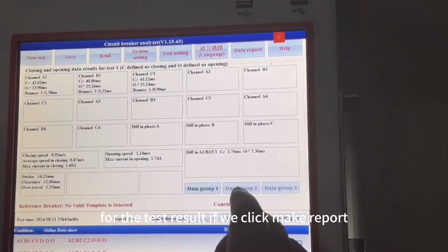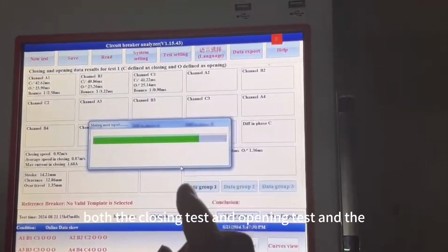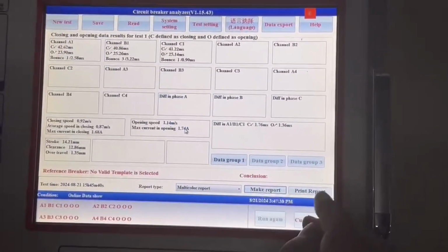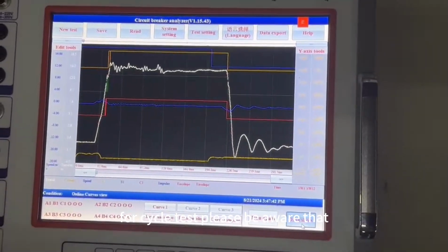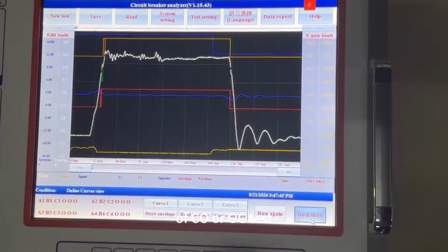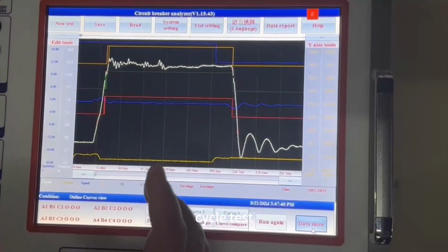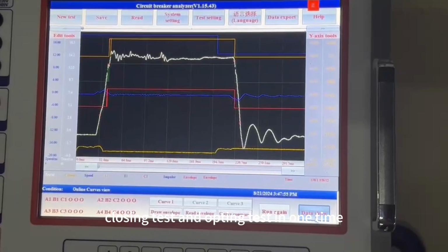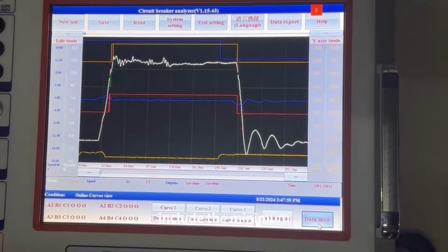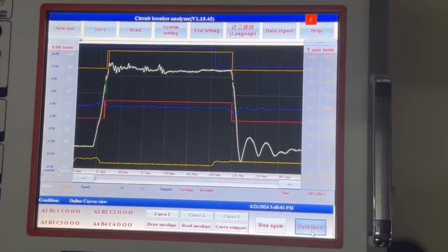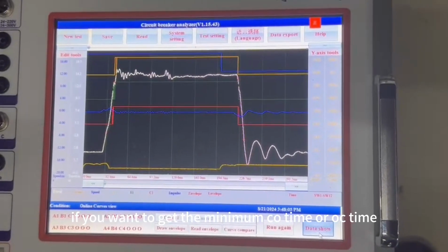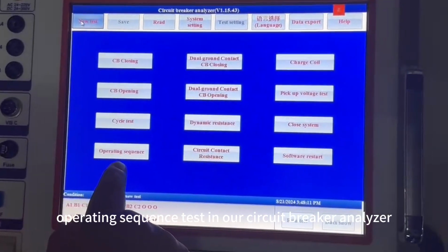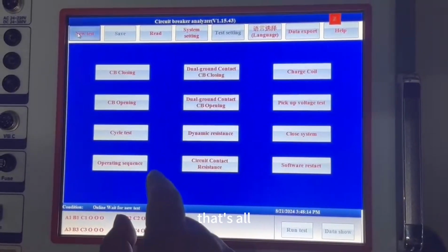For the test result, if we click make report, both the closing test, the opening test and the CO test curves will be saved in one report. For circuit tester, please be aware that it is different from CO tester or OC tester. Circuit tester in our circuit breaker analyzer means finishing the closing test and opening test in one time, but it does not include the minimum CO time or OC time. If you want to get the minimum CO time or OC time, you should use the operating sequence test in our circuit breaker analyzer. That's all.